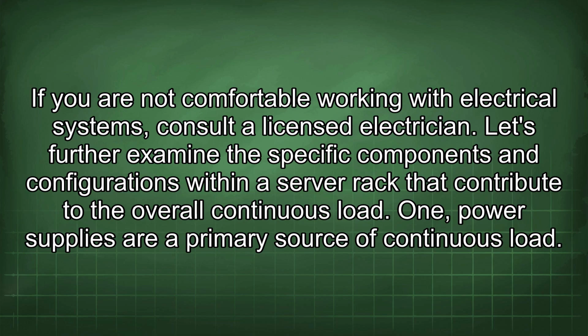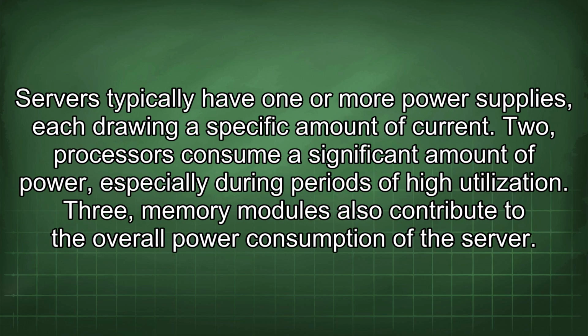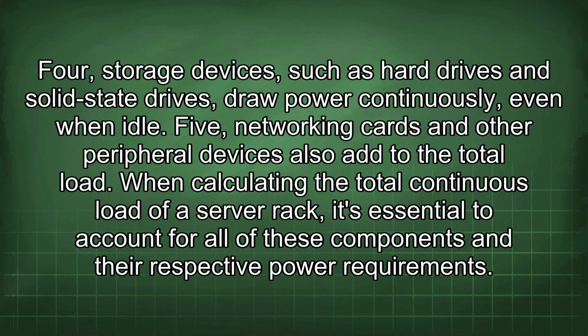1. Power supplies are a primary source of continuous load. Servers typically have one or more power supplies, each drawing a specific amount of current. 2. Processors consume a significant amount of power, especially during periods of high utilization. 3. Memory modules also contribute to the overall power consumption of the server. 4. Storage devices, such as hard drives and solid-state drives, draw power continuously, even when idle. 5. Networking cards and other peripheral devices also add to the total load.